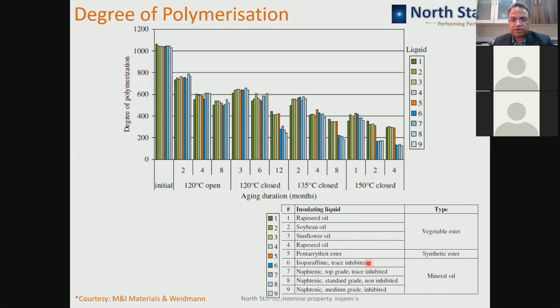Then isoparaffinic trace inhibited mineral oil, dark blue color. Then naphthenic oil, mineral oil. Then naphthenic standard grade mineral oil, non-inhibited, and then naphthenic medium grade inhibited. So such 9 samples were taken, insulation was put into these different kinds of oils, and then the polymerization test was performed, and this is the trend observed.